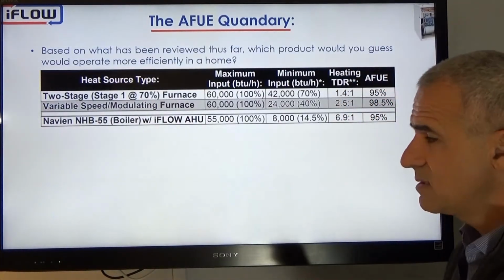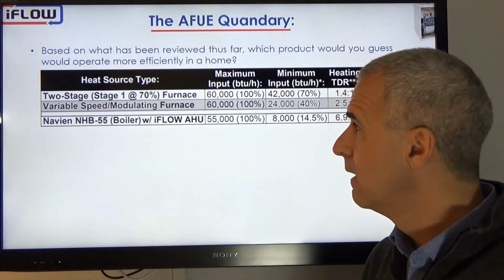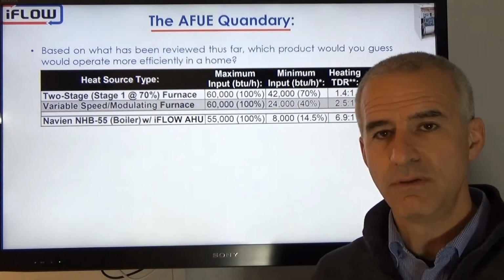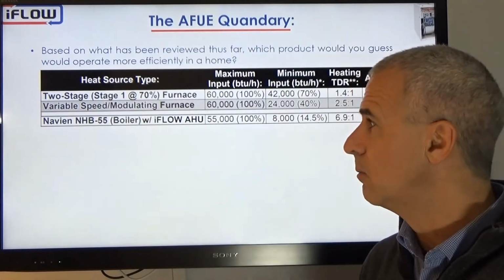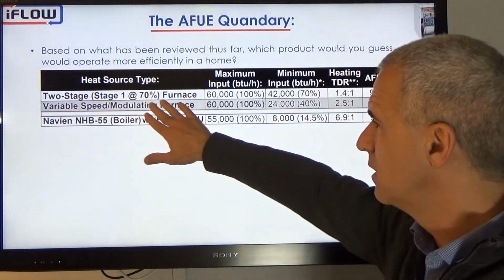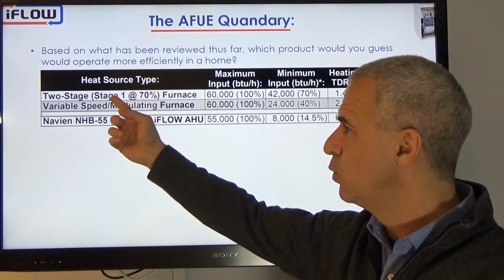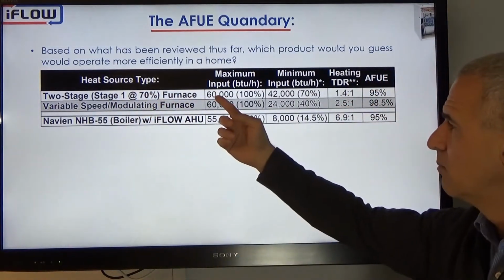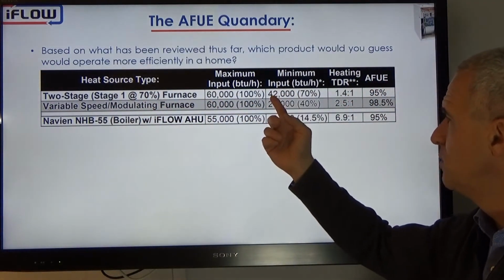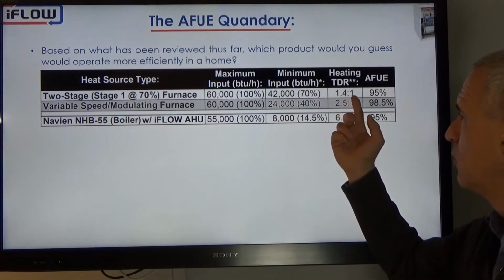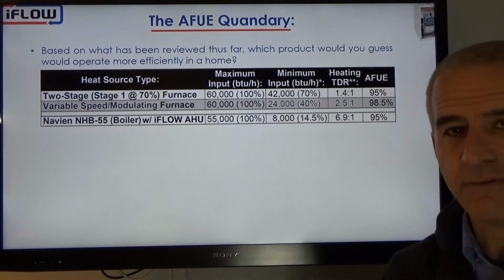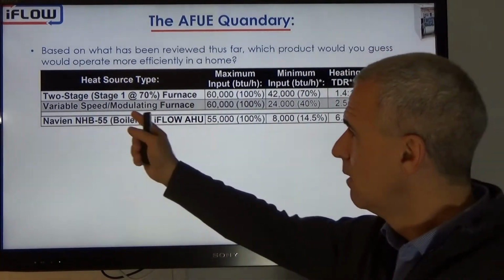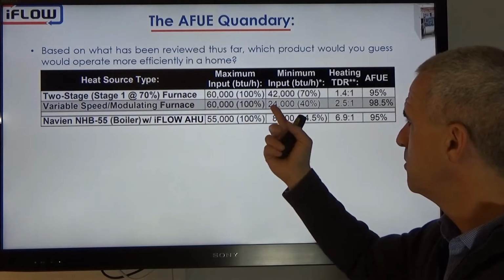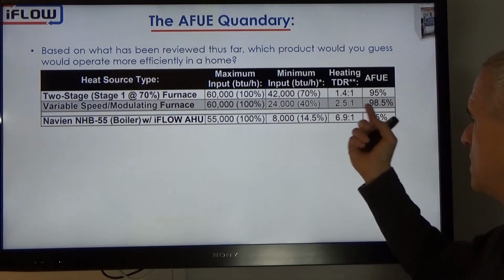So based on what we've reviewed thus far, which system do you think would operate more efficiently in a home? Let's look at the 2-stage furnace with minimum input, or stage 1, at 70%. So maximum 60,000, minimum 42,000. Again, that 1.4 to 1 turn down ratio with an AFUE of 95%. And then we're going to look at the modulating furnace as well, 60,000 BTUs, minimum input 24,000 BTUs. This one is rated at 98.5 right off the Energy Star site.